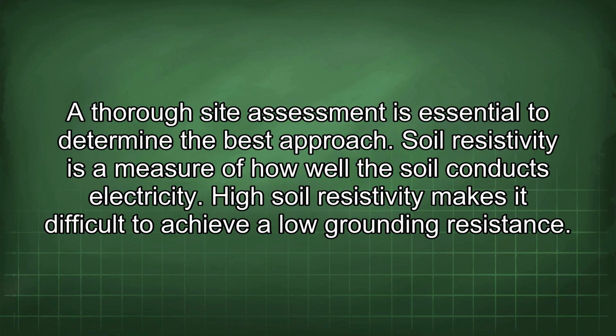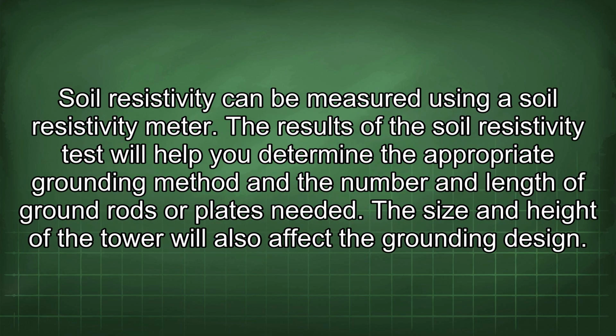Soil resistivity is a measure of how well the soil conducts electricity. High soil resistivity makes it difficult to achieve a low grounding resistance. Soil resistivity can be measured using a soil resistivity meter. The results of the soil resistivity test will help you determine the appropriate grounding method and the number and length of ground rods or plates needed.